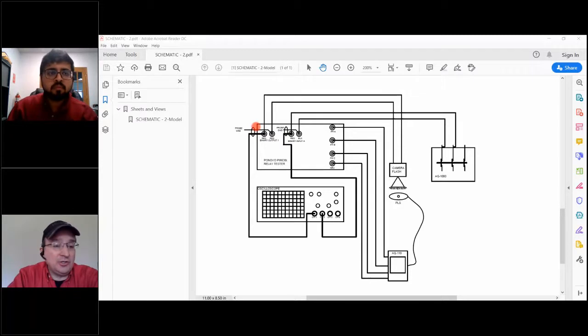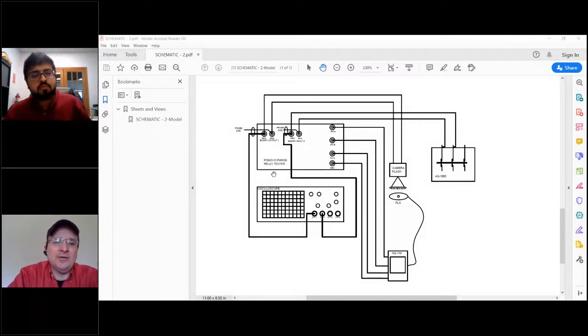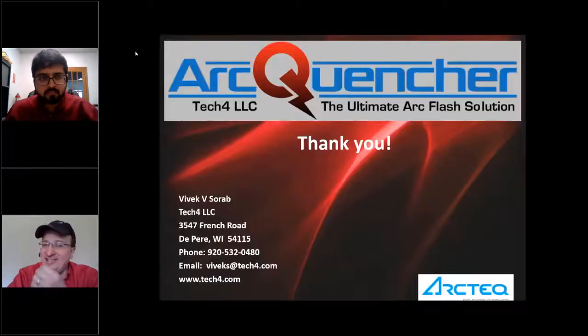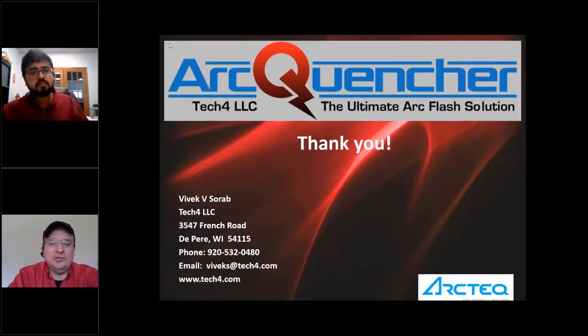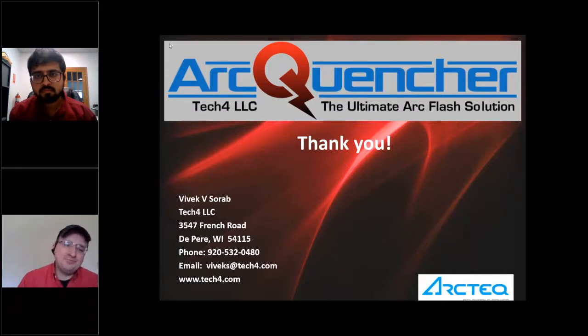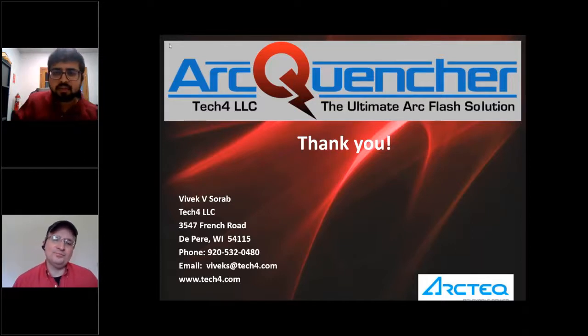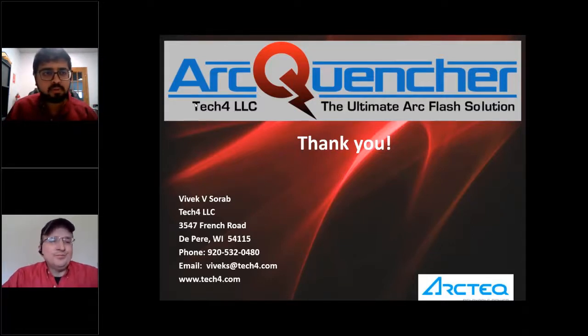So the answer is, if you have an application in Europe or in other parts of the world that accept or expect IEC distribution equipment, Siemens new switchgear offers that solution. It's not available in a retrofit solution. It's not available in other people's equipment. And most importantly, right now, it's not available in North America. Good question. I did not know that. That was something new. In North America, we're still ANSI IEEE land here, so you don't normally see pure IEC distribution equipment installed in the United States or Canada.